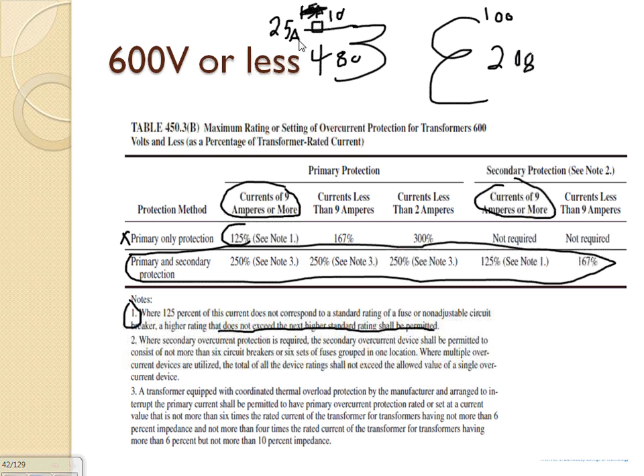By the way, if you don't know if it's a standard fuse, where do you go? There's an article, 240.6, that lists all the standard fuses that are approved by the code. 240.6. The second one here, I'm going to use 125. So this is 125. That will give me 125 amp. Done. So I have my 125 amp on the secondary and 25 amp on the primary. Good to go on this.